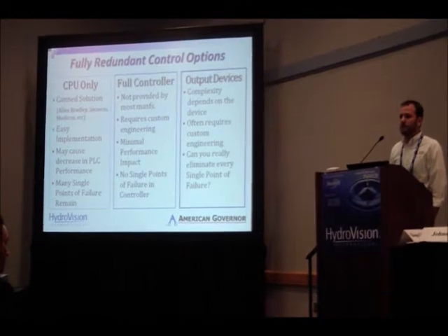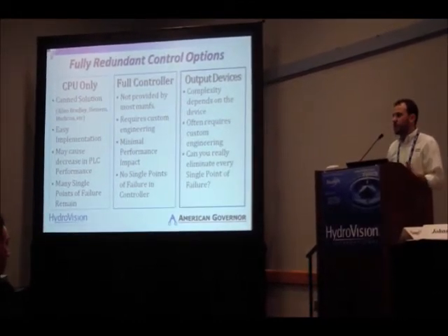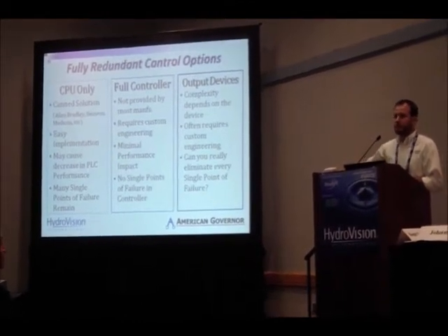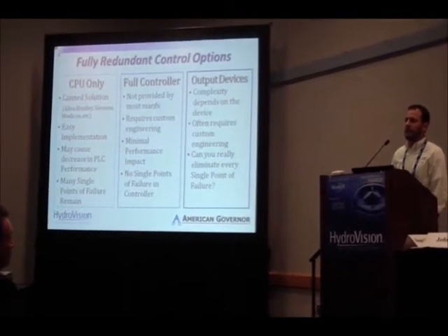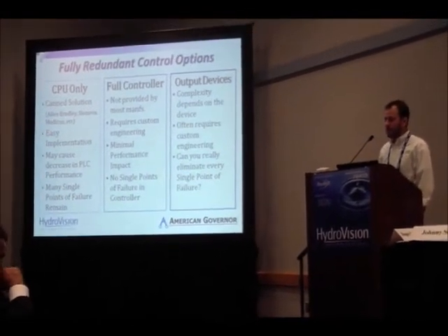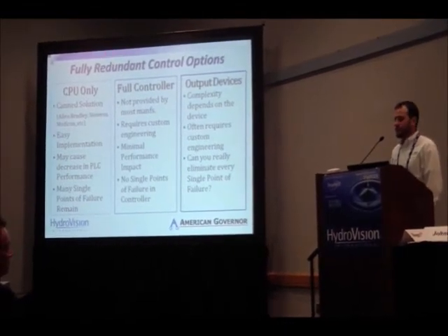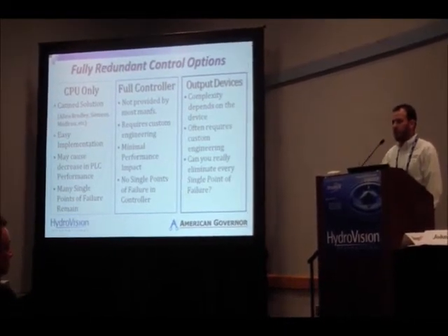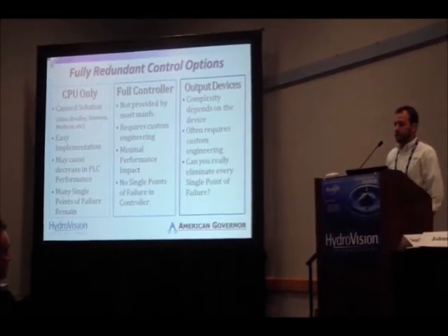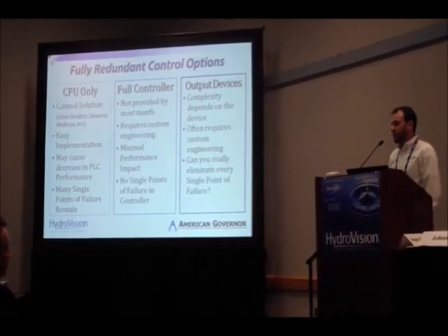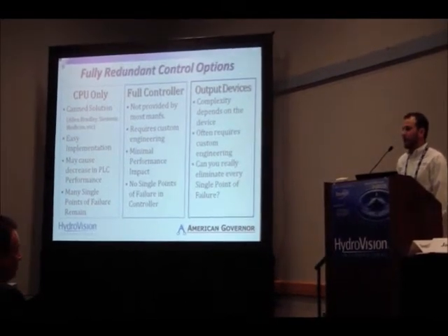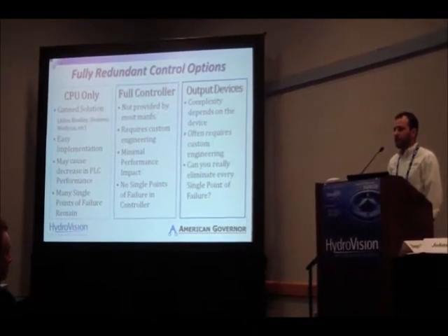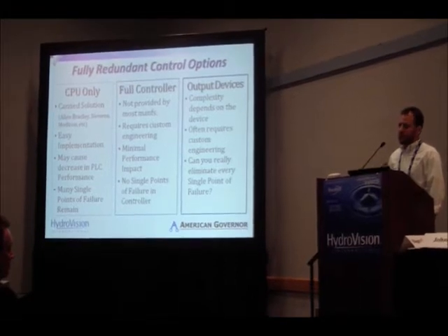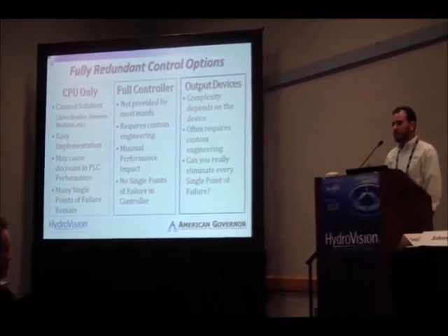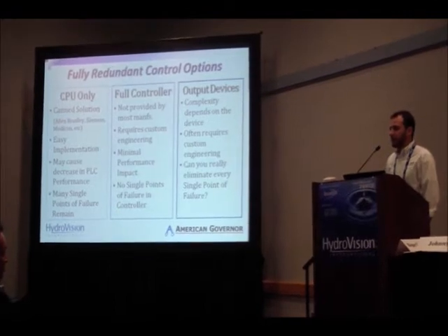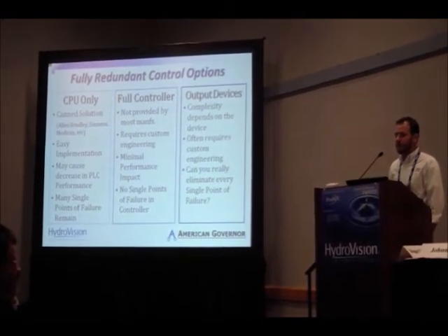This still leaves single points of failure. These 2 controllers come to consensus and say, okay, we're going to open this actuator. Well, what happens if the relay that opens the actuator fails? Or what happens if the valve that opens the actuator fails? And this is where things really start getting into a gray area. You're kind of going down the rabbit hole of where do we stop? And you need to look at the device, look at the likelihood of it failing, look at the cost of it failing. You'll often see redundant hydraulic controls. Less often we'll see redundant relays because of fail-safe logic and how they operate. It can get really complicated and give intermediate states of failure.